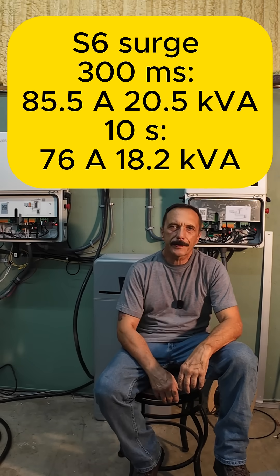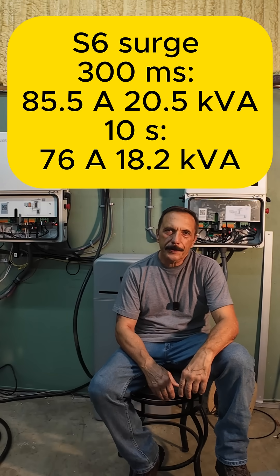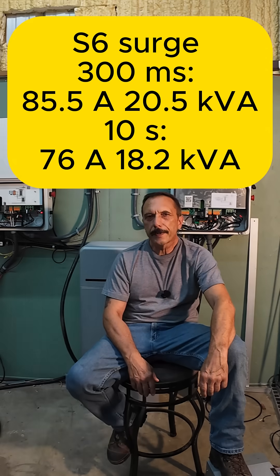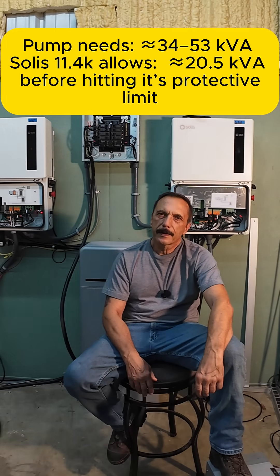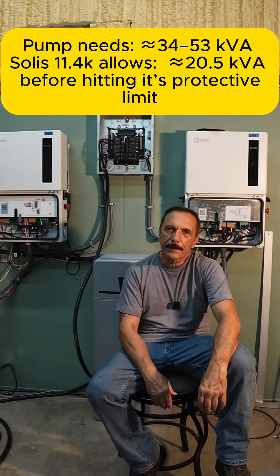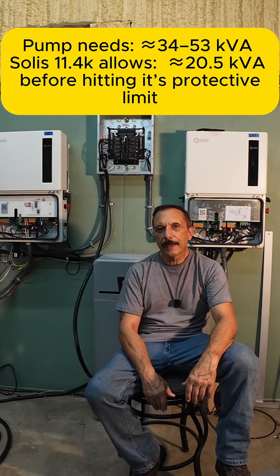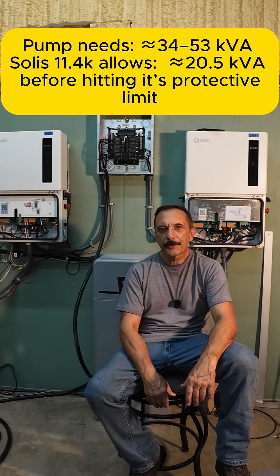The Solis S6 can burst 85 amps for 300 milliseconds — that's about 20 kVA — and 76 amps for 10 seconds, that's about 18.2 kVA. So that 5 horsepower motor needs way more current than the Solis S6 is rated for. If the pump needs 34 to 53 kVA right at the start, the inverter's going to hit its current limit, voltage is going to sag, torque drops, and the motor won't start.